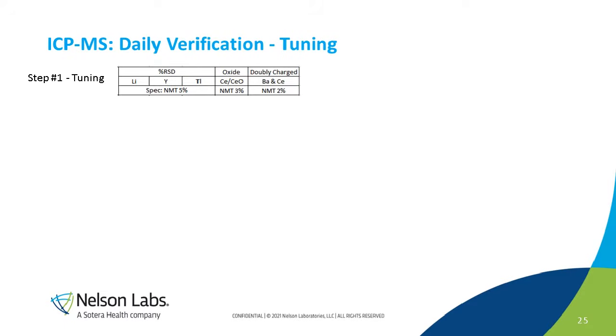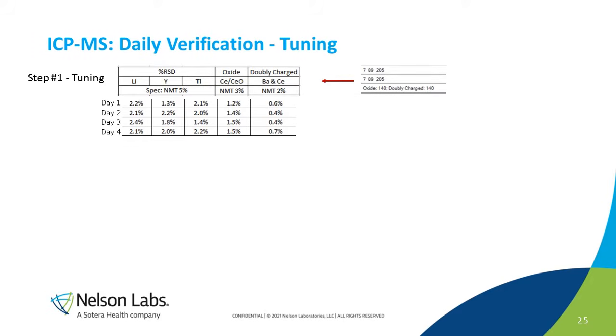So all these steps we call tuning, and obviously this tuning requires some parameters. We use a tuning solution, and we use some elements for that: lithium, yttrium, and thallium. Now we check the masses 7, 89, and then 205. They could be determined here. The specification is that when we introduce this tuning solution into the system, it should be below NMT 5% for single element, or oxide NMT 3%, and then doubly charged should be below 2%.